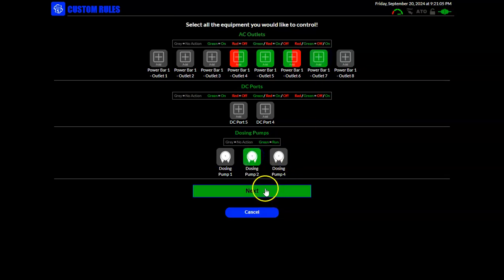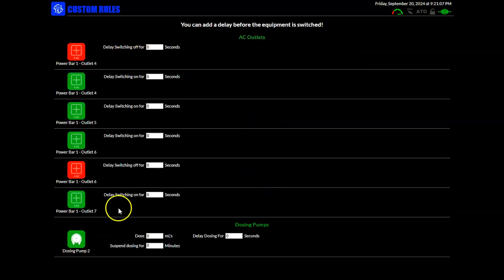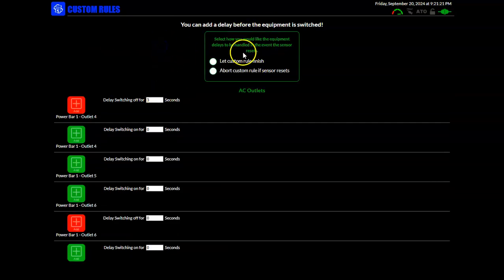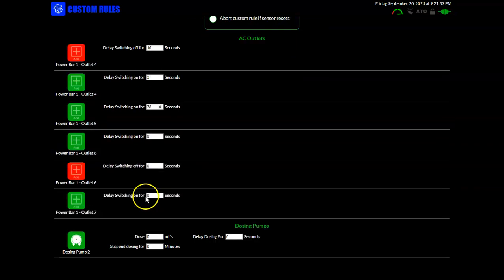And we can do a dose. So now we have the outlets that we selected. So maybe we want to delay so you can stagger things. So now the custom rule is going to trigger after 60 seconds when the pH stabilizes. And then see, you get a new setting here. I'll explain that shortly. So now after the custom rule actually triggers, it's going to wait 10 seconds before this goes off. It'll turn this one on in 3 seconds. It'll turn this one on in 30 seconds so you can stagger it.